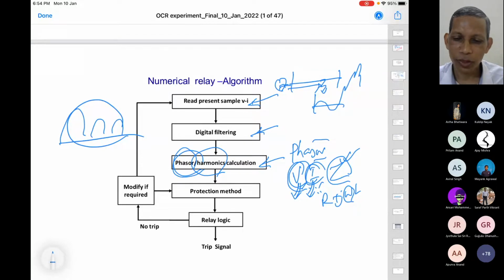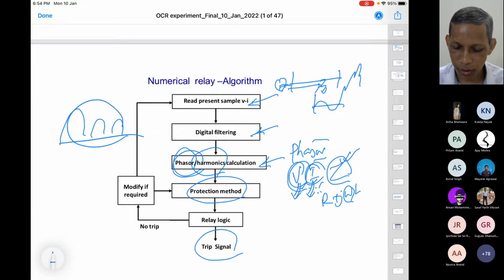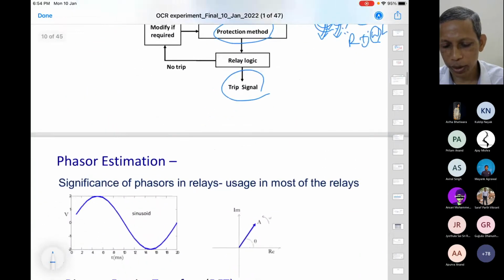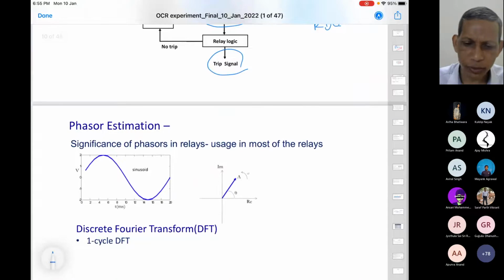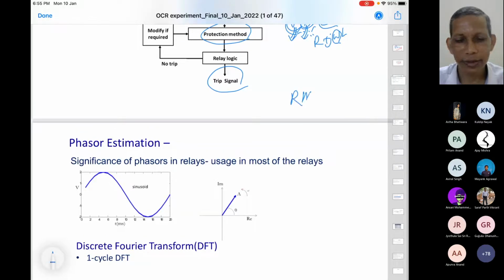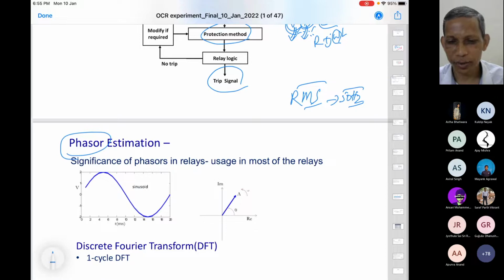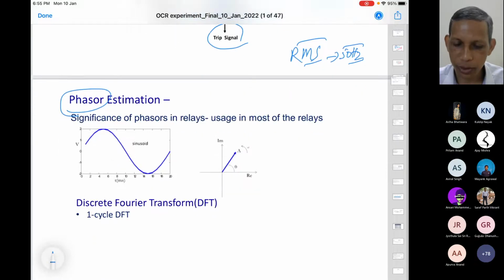So that's my point. We essentially require phasor estimation, and then the protection logics, or relay logics, in terms of that, and then make a trip or no trip, no signal. So this is the background of how the numerical relay acts. To have a basic idea of how the phasor is computed, I told you not to go for a simple RMS. RMS is inclusive of the whole signal component. Rather, you extract the corresponding 50 Hz component, the fundamental, and then peak by root 2 gives you the RMS of that single signal. So here the purpose is how to get the phasor. It is a digital filter, a Fourier filter in general, that is used for this. There are other options also.